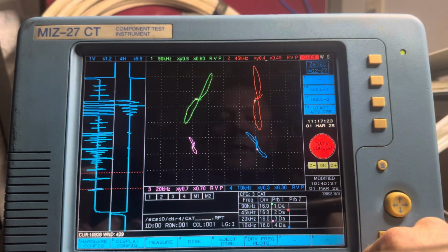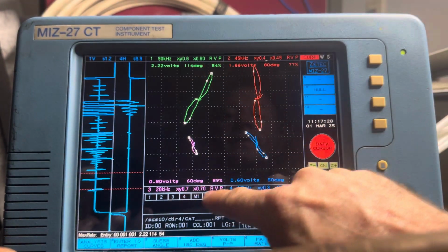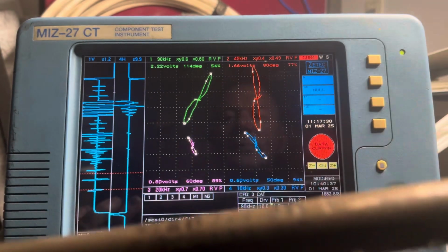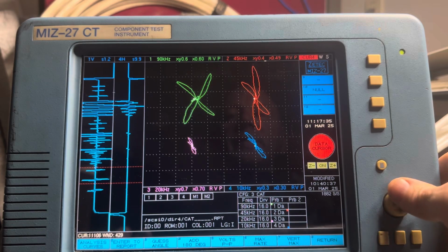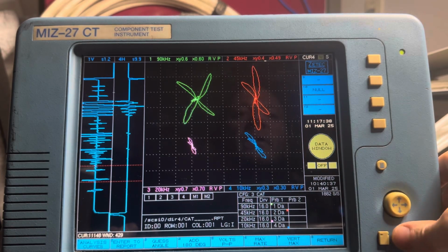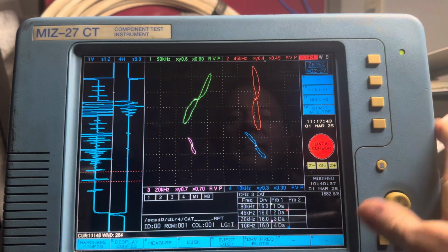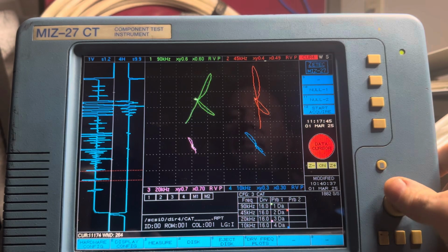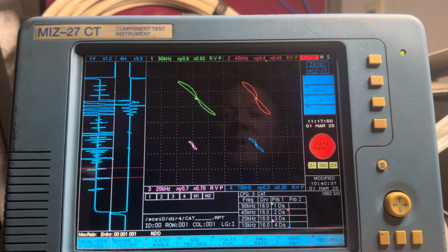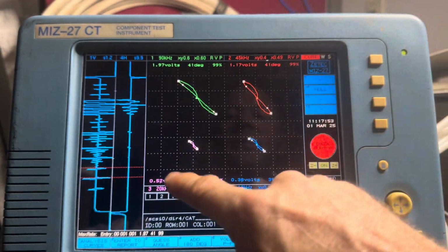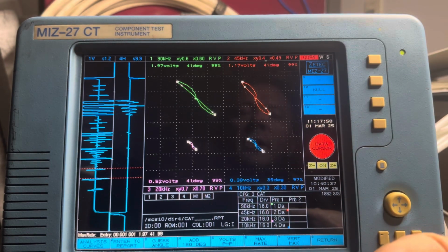Same thing if we go measure it. There we go: 114, 80, 60, and 50. It's rotating counterclockwise with decreasing frequency. Textbook. Okay, then we go to the 100. Now here's where I'm going to have to crank my window size down a little bit because we're going to start to get into the busy part of this reference standard. So that 100, if I remember correctly, I should have set that fairly close to 40. 41, 41, 41, 39. Okay, so that's normally where you calibrate your single 100% through-wall signal.